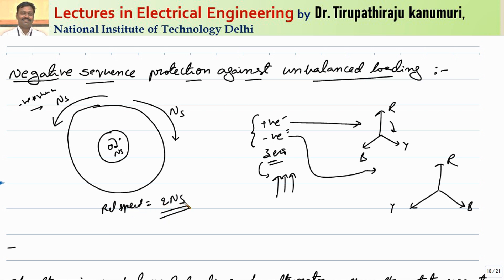Because of this relative speed of 2ns, a dynamically induced EMF is induced in the rotor, since the induced EMF is proportional to speed. Even though the negative sequence flux is small, the speed is very high, so a very large EMF and consequently large currents are induced in the rotor conductors, as well as increased core losses.